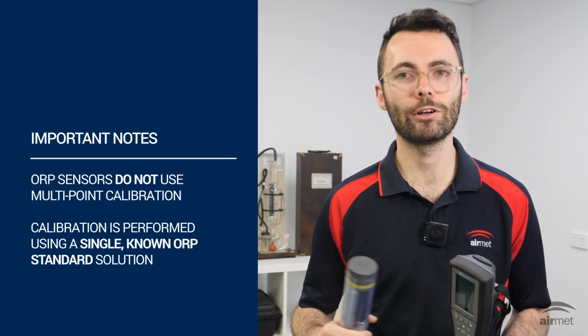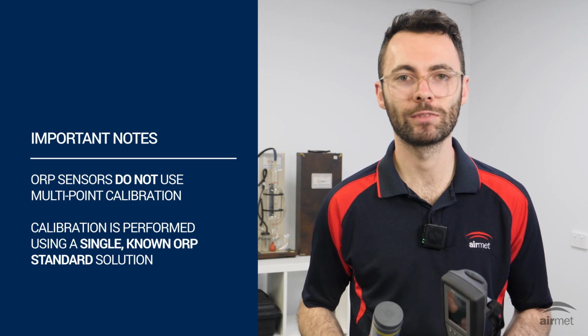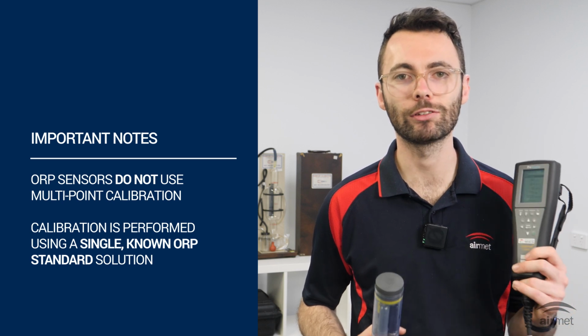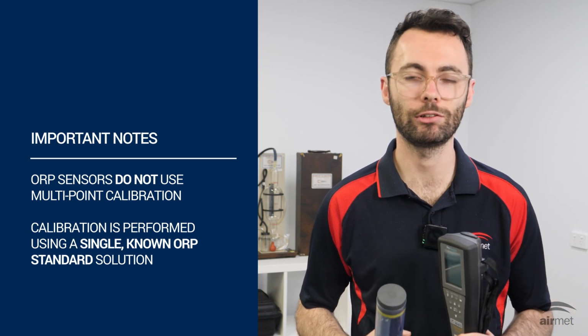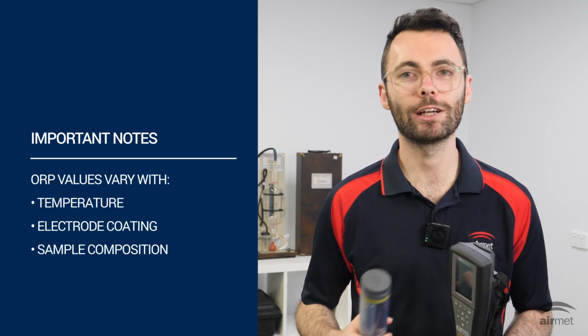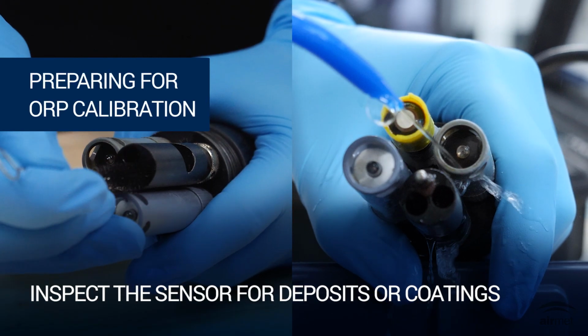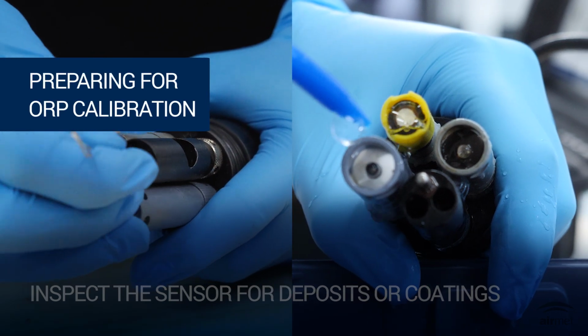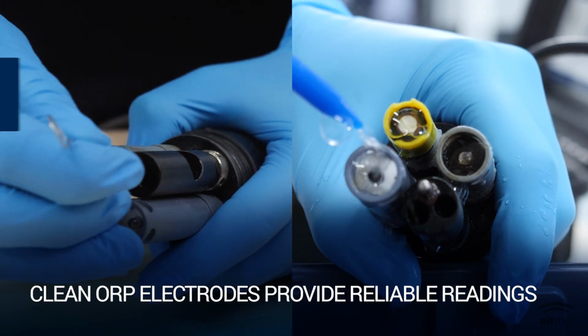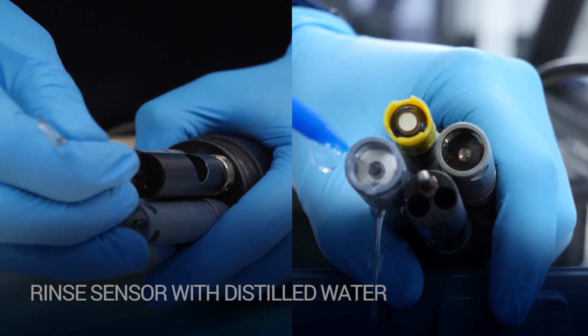ORP sensors do not use a multi-point calibration. Instead, calibration is performed using a single, known ORP standard solution. ORP values vary with temperature, electrode coating, and sample composition. Before calibrating, inspect the sensor for deposits or coatings. ORP electrodes must be clean and in good condition to provide reliable readings.